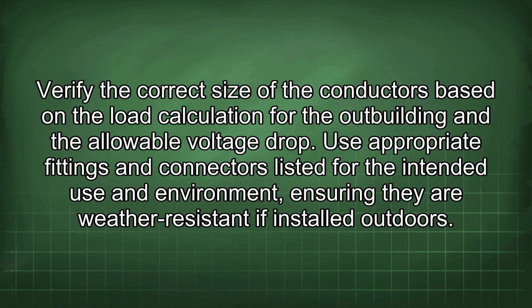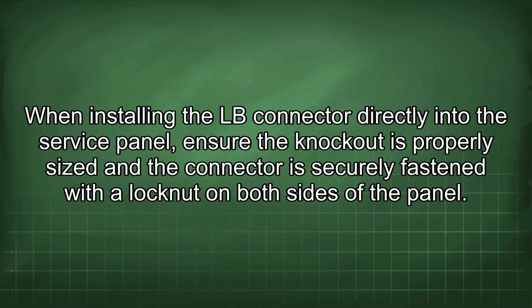Verify the correct size of the conductors based on the load calculation for the outbuilding and the allowable voltage drop. Use appropriate fittings and connectors listed for the intended use and environment, ensuring they are weather resistant if installed outdoors. When installing the LB connector directly into the service panel, ensure the knockout is properly sized and the connector is securely fastened with a lock nut on both sides of the panel.